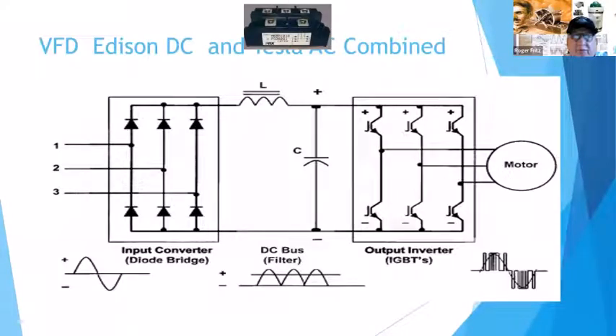So then what came forward is the actual variable frequency drive technology, which is basically a bridge diode front end. They typically have a reactor or a choke coil in here to slow the current down, and then they have capacitors to build DC. So that's what Edison was originally talking about, that everything should be DC, DC, DC. But you can't transform DC or control it like you can with AC power. So then there are output transistor blocks, which is really the simplicity of what we're dealing with, and that goes to the motor.